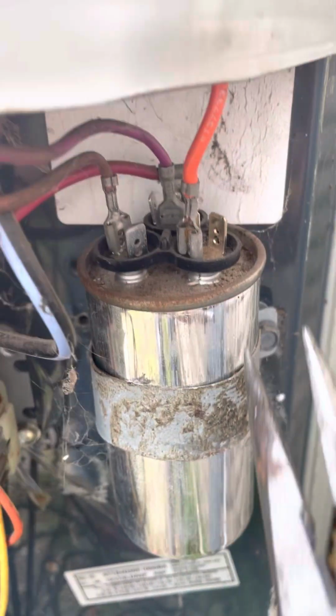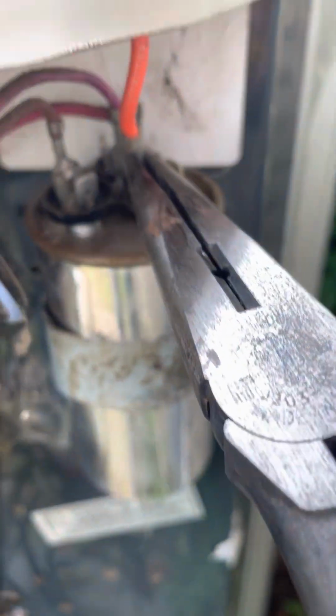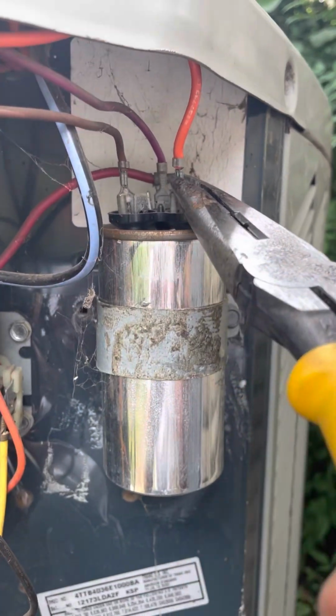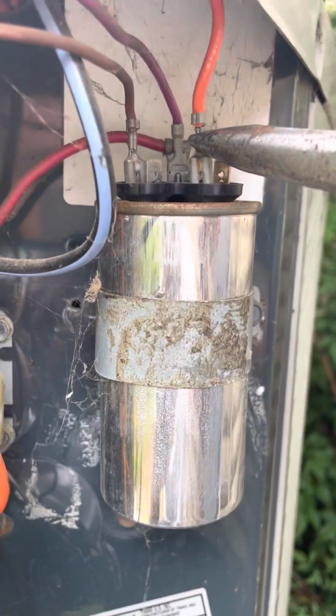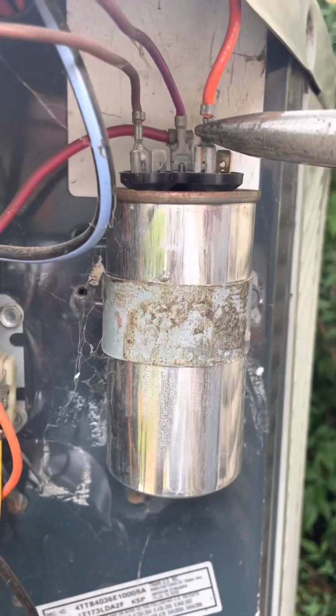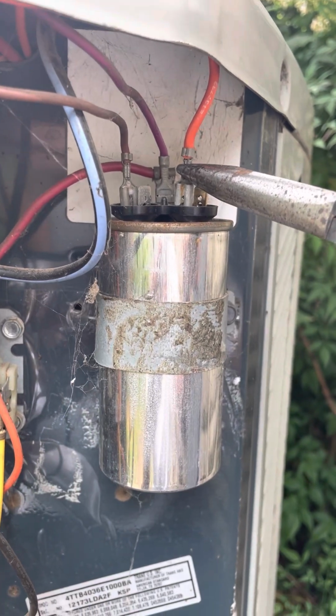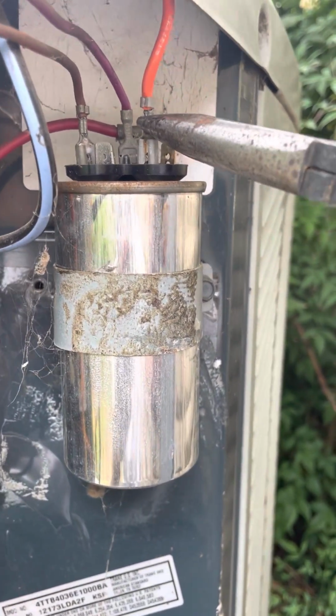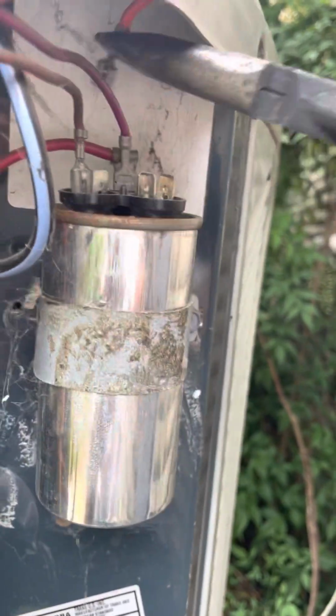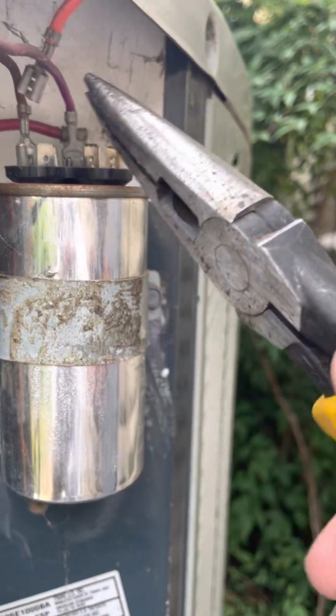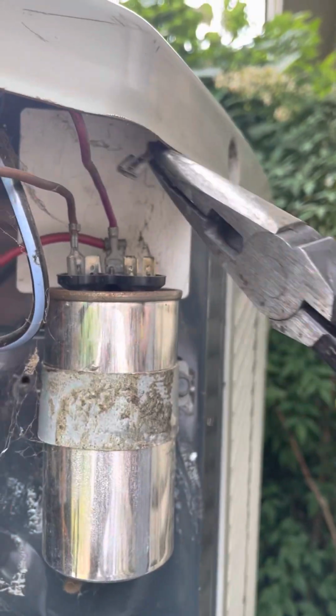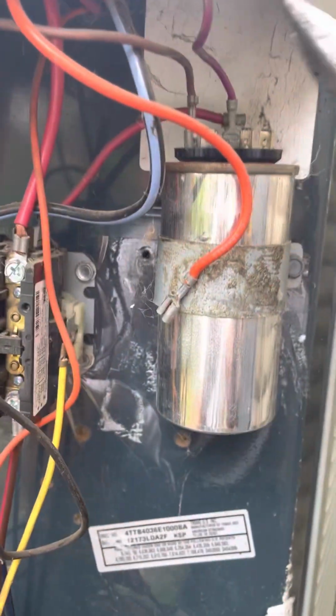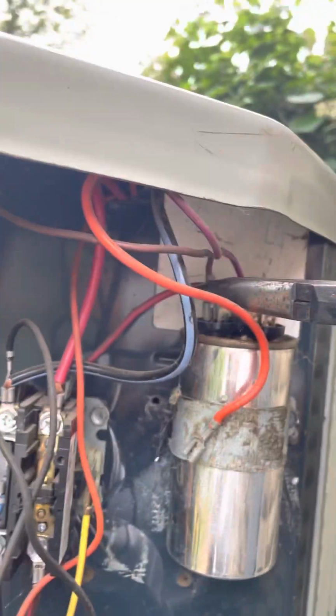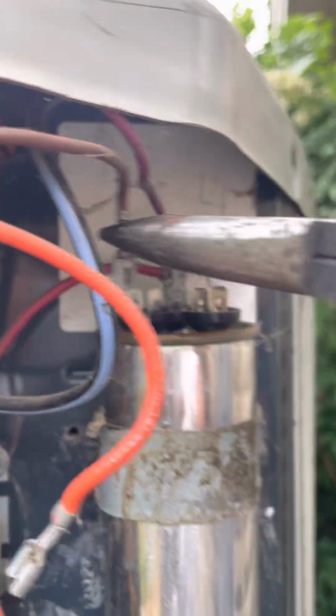Alright, so we're just going to disconnect here. I'm going to pull the wires off. Make sure you take a picture of where the wires go, just so that when you put the capacitor back, you can put the wires back in the correct spot. So I'm just going to take that off and set that aside. That wire I believe came from the compressor. This brown wire comes from our condensing fan motor. You can see it here. Just going to work that off.